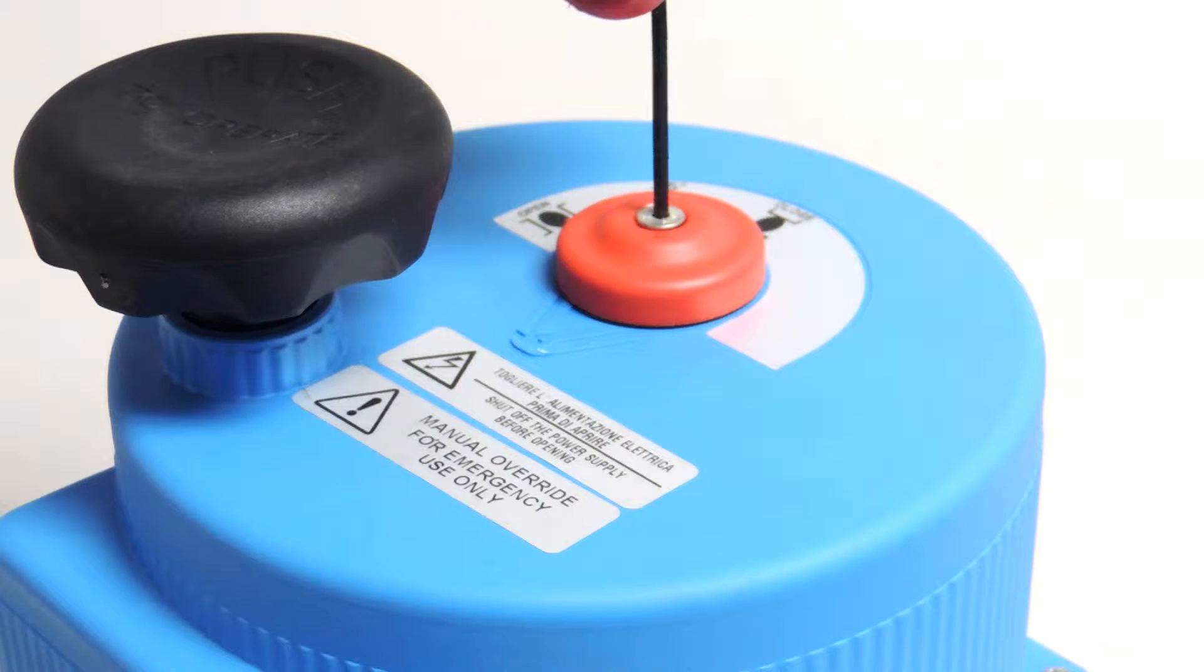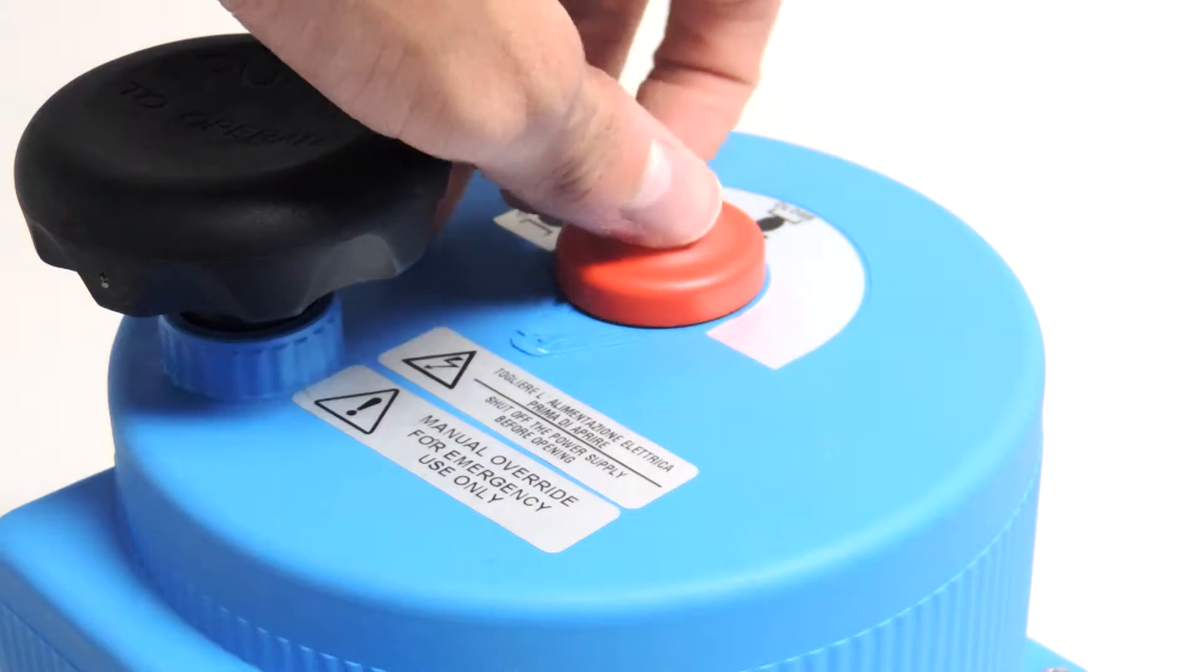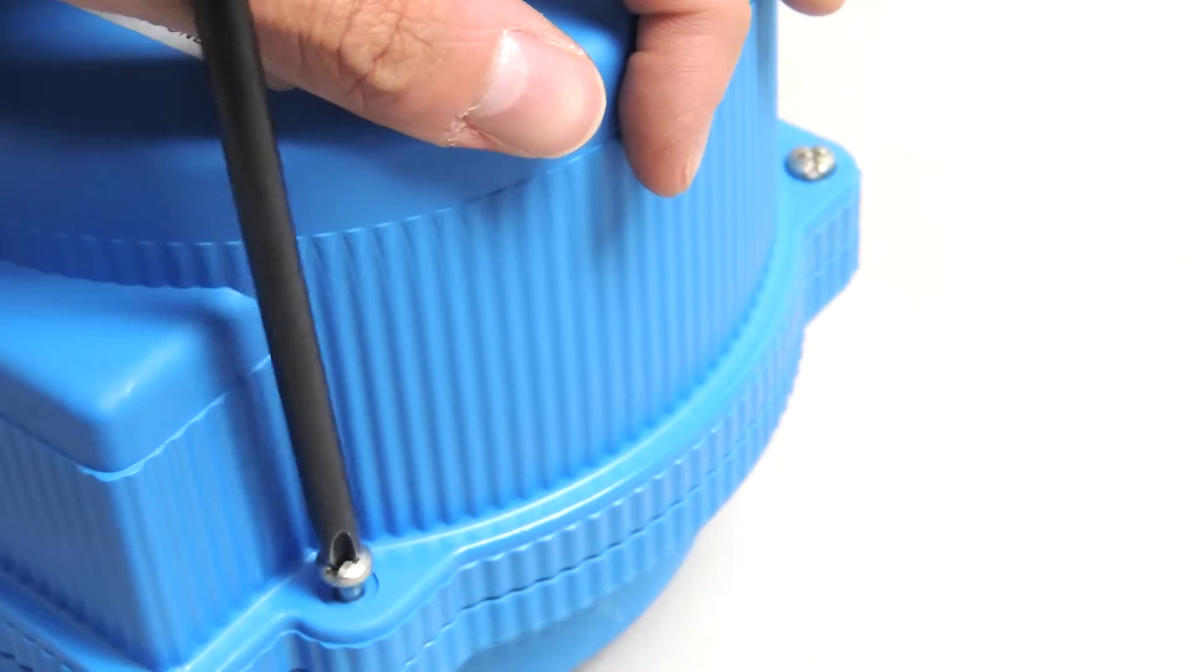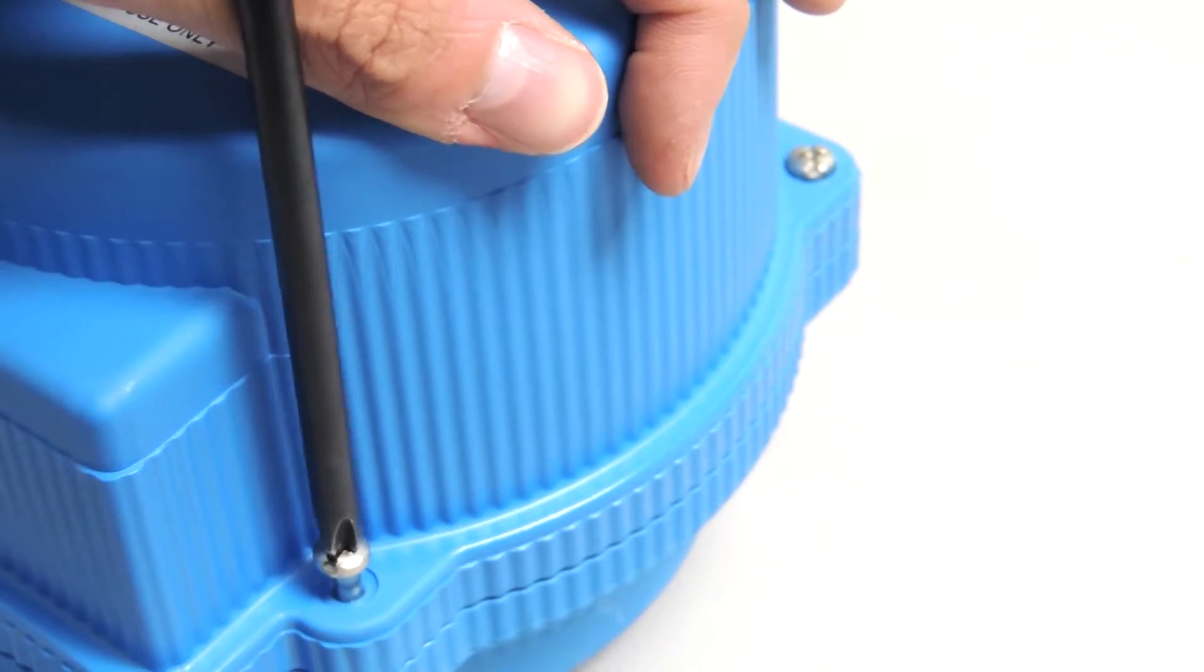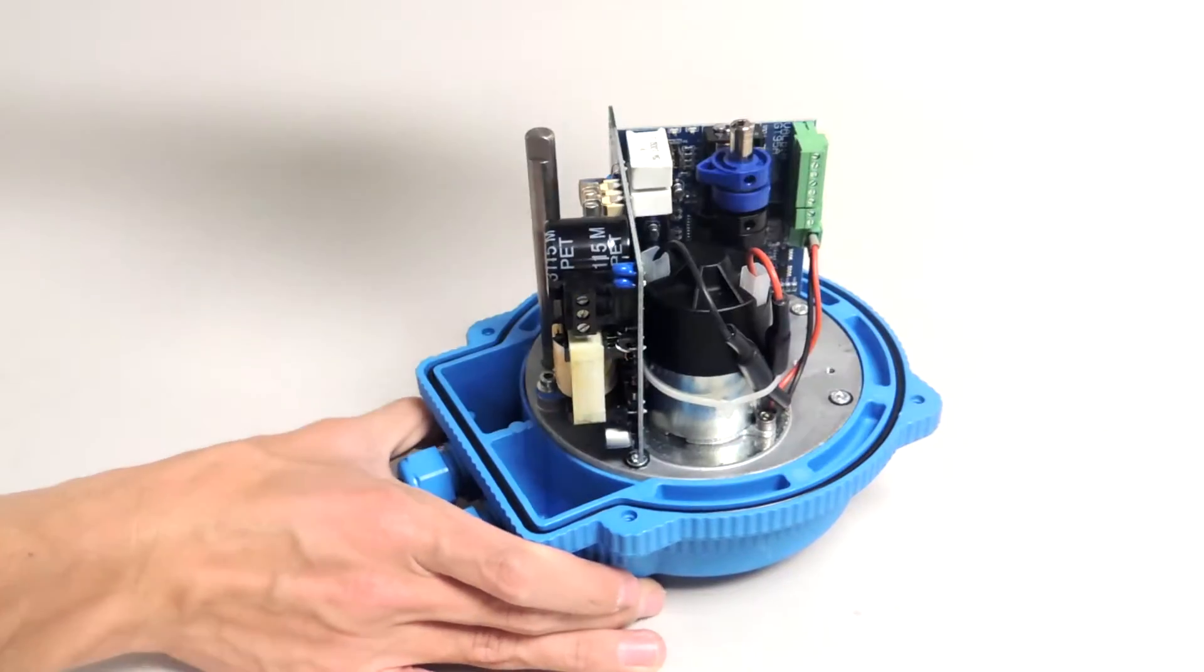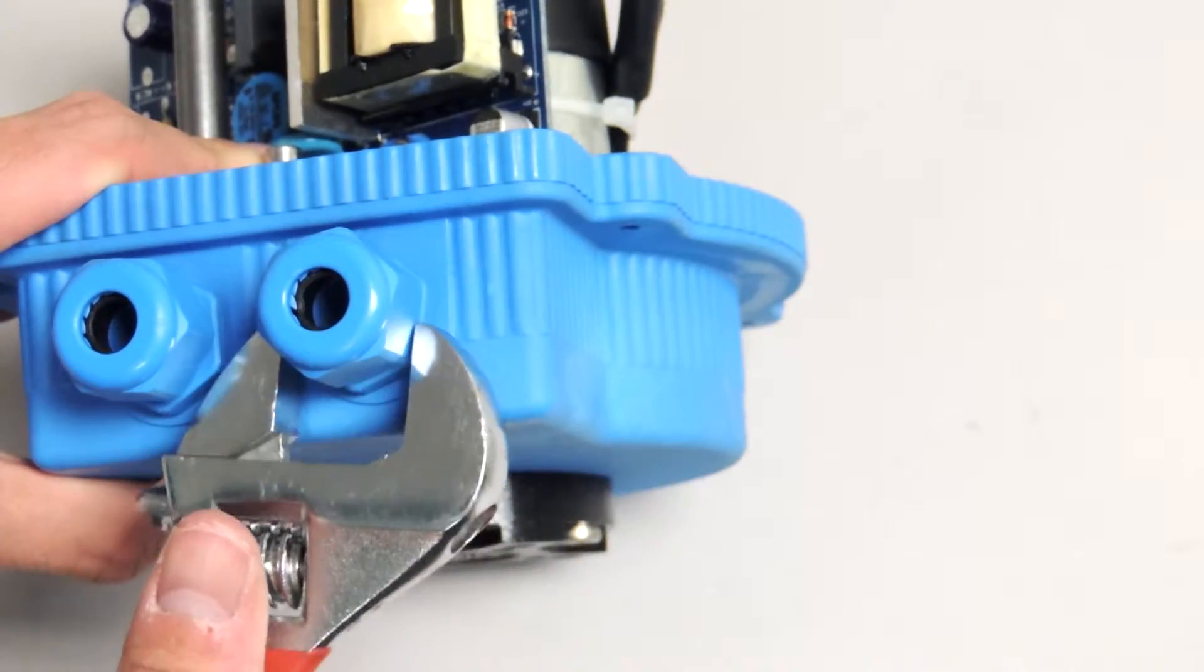Unscrew the bolt on the red indicator dial and then remove it from the unit. Then, unscrew the four screws holding the shell together and put the top part off to the side. Remove one of the conduit ports from the housing and replace it with the conduit port adapter.